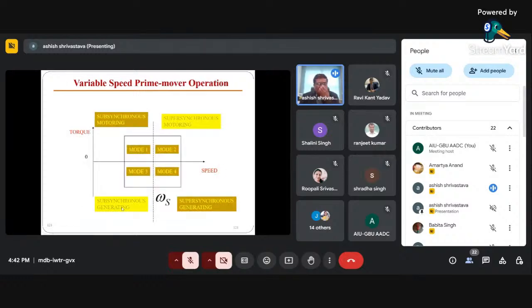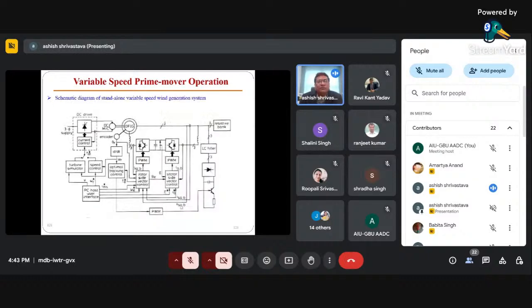Then with the DFIG, the main advantage, as I said, is that you can achieve four quadrant operation, modes 1, 2, 3, 4. At sub-synchronous speed, you can achieve motoring mode as well as generating mode, and at super-synchronous speed, you can also achieve motoring mode and generating mode. But this is only possible because you can have a bidirectional power flow. So you can have motor or generator operation, anything you can achieve.